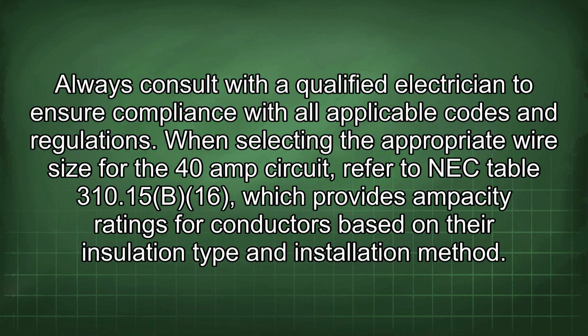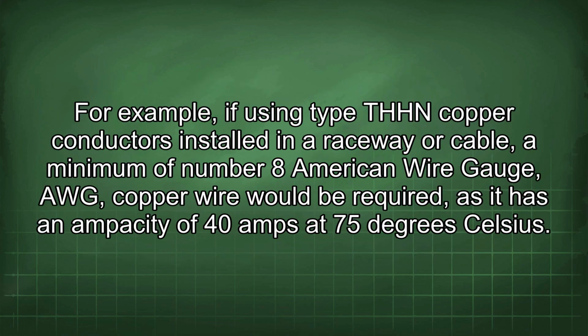When selecting the appropriate wire size for the 40 amp circuit, refer to NEC Table 310.15(B)(16), which provides ampacity ratings for conductors based on their insulation type and installation method. For example, if using type THHN copper conductors installed in a raceway or cable, a minimum of number 8 American Wire Gauge (AWG) copper wire would be required, as it has an ampacity of 40 amps at 75 degrees Celsius.